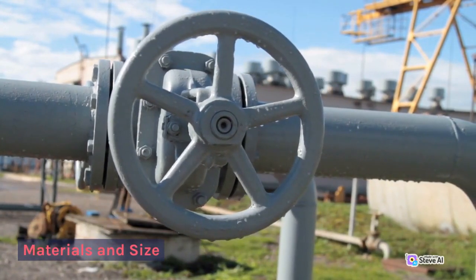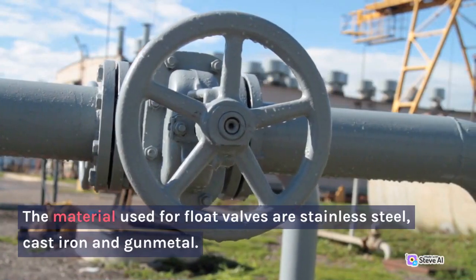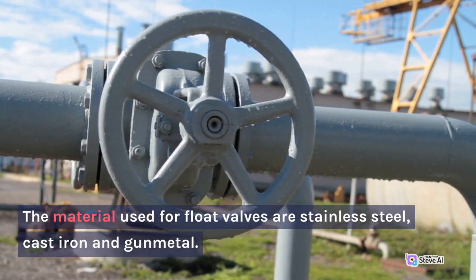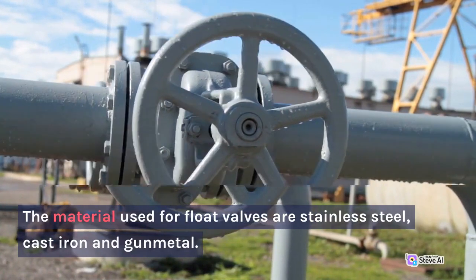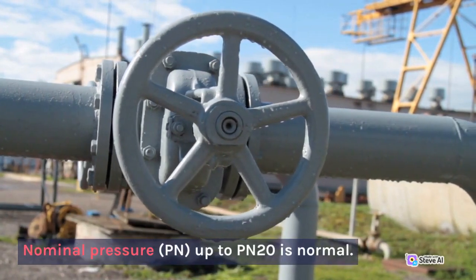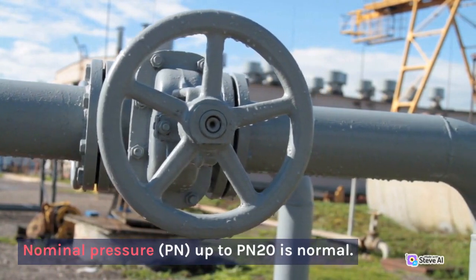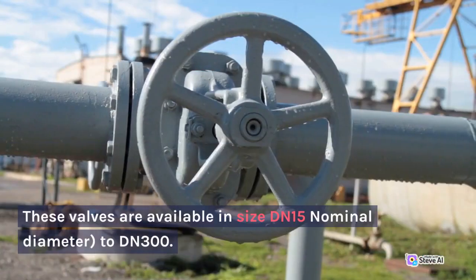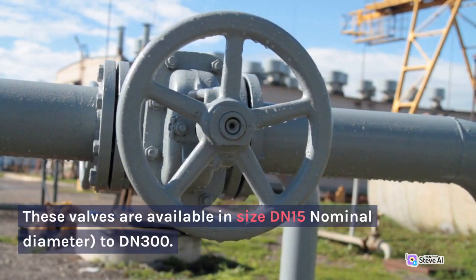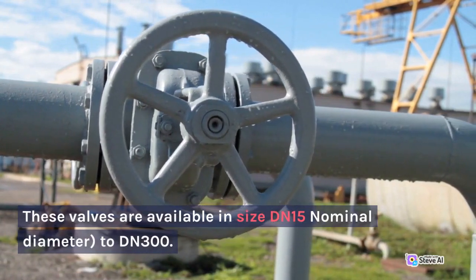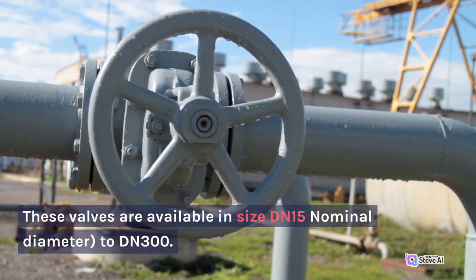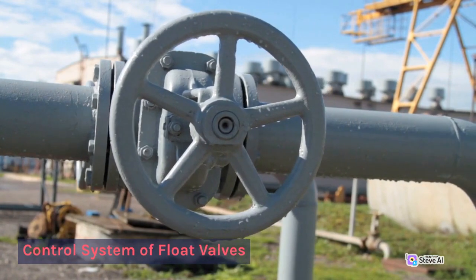Materials and size. The materials used for float valves are stainless steel, cast iron, and gunmetal. Nominal pressure, PN, up to PN 20 is normal. These valves are available in sizes from DN 15 nominal diameter to DN 300. Control system of float valves.